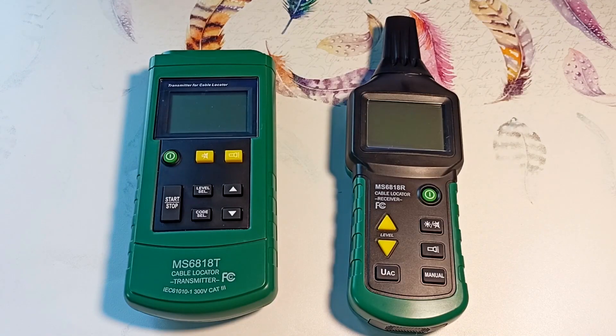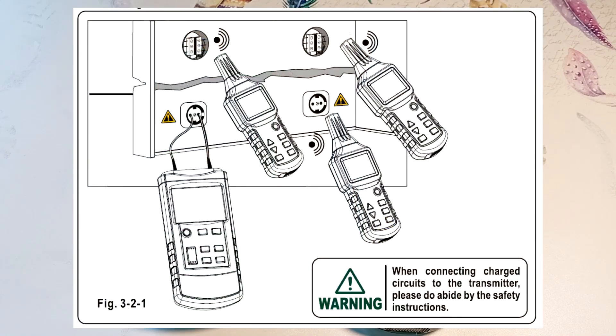Now let's look at the two-pole connection of the device and its capabilities. The detection depth can reach 50 centimeters. This figure shows wiring location detection. The circuit can be energized or not. We connect the generator to the outlet of the circuit that we want to trace.